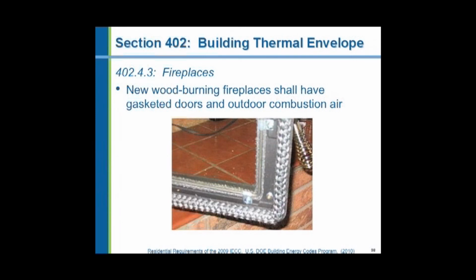The next section in the code requires new wood-burning fireplaces shall have gasketed doors and outdoor combustion air. Well, there's many types of fireplaces. There are fireplace inserts. There are gas logs. There are corn burners. There are pellet burners. The code says new wood-burning fireplaces. So that means what it says. So if you have a fireplace with a gas log, it doesn't have to have a gasketed door and outdoor combustion air. But the principle of this section in the code is to reduce infiltration.